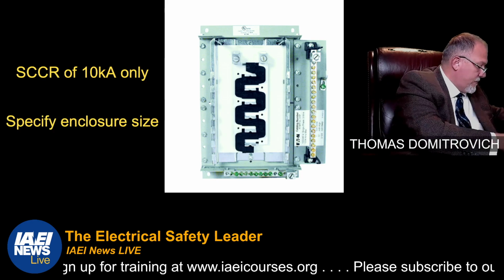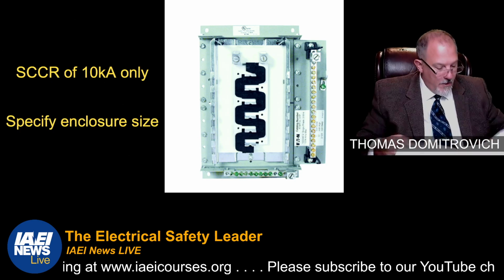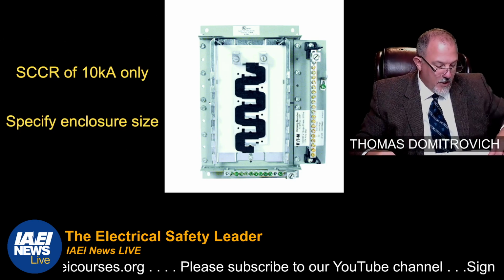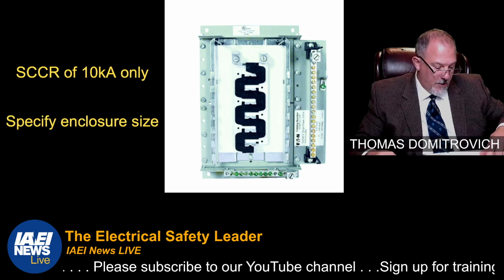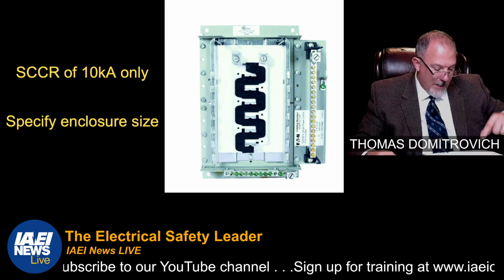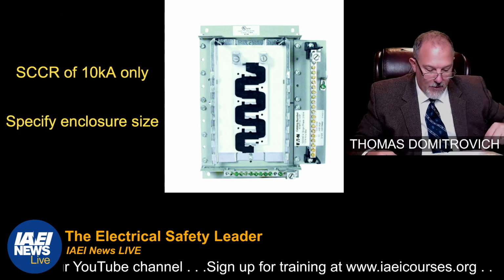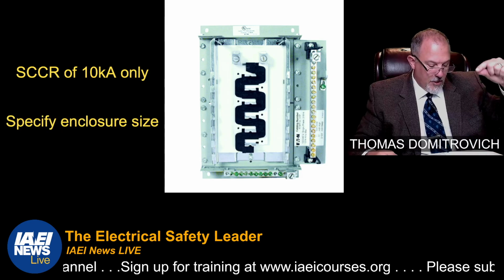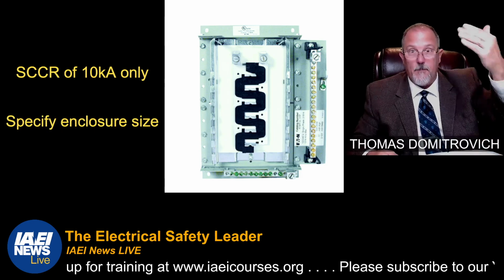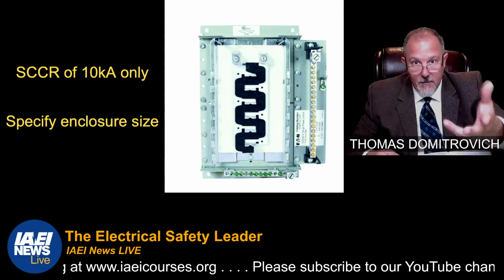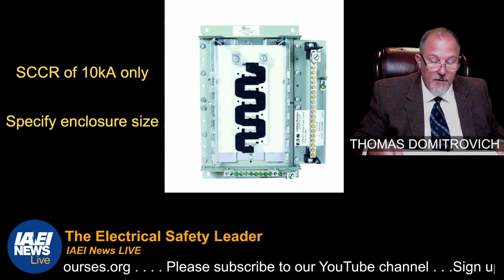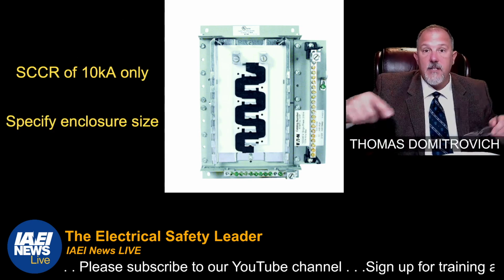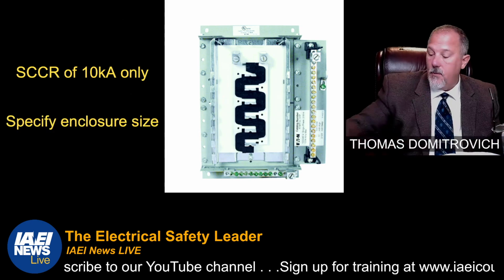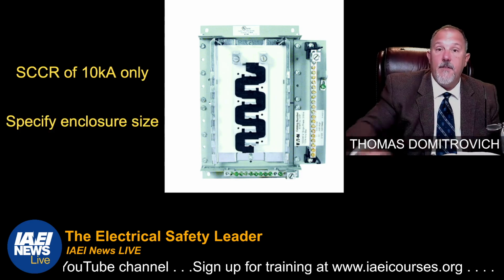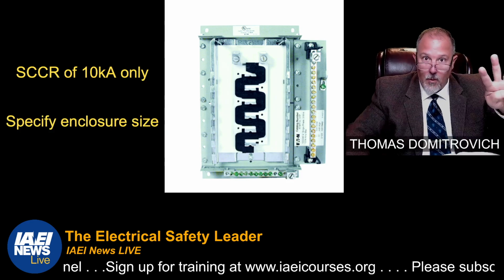Remember, in Part 4 construction, they'll talk about panels, bus bars, protection of circuits, component parts, maximum number of overcurrent devices, and wire bending space within an enclosure containing a panel board. There's A, B, C. There's a top and bottom wiring space. There's a side wiring space. There's a back wiring space. So you've got to think about all that. The manufacturers of these devices will tell you the size of the enclosure, or you tell them the size of the enclosure, the depth, and all that good stuff, and they'll tell you what interiors will fit in there, taking care of that wire bending space that's in part 4 of Article 408.